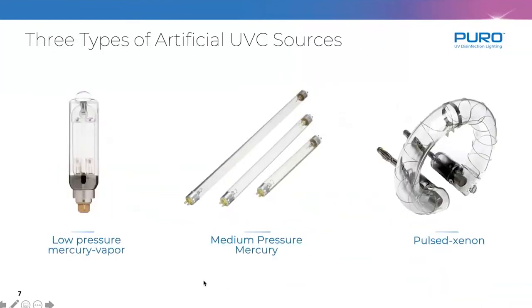This gives you an idea of the different technologies. You have low-pressure mercury and medium-pressure mercury — both look like fluorescent tubes but with a blue hue. And then pulsed xenon. These are the only technologies you'll see today for whole-room disinfection that are really effective. The mercury-based systems are dramatically lower energy — think of mercury as a hose. Pulsed xenon is about 4,000 times the energy in short microbursts — think of it more like a pressure washer, concentrating that energy and doing more with less. Because the pulses of light are so short, you don't get the same damage to materials in the space.